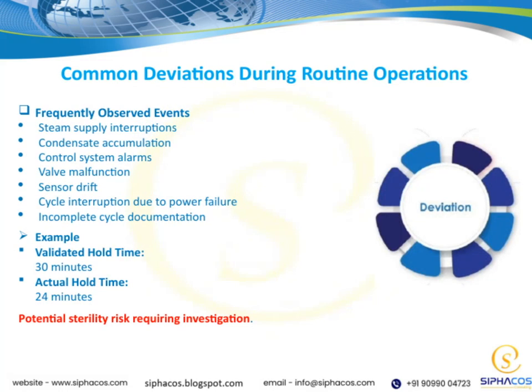When we talk about common deviations during routine operations, these are the events we see most often. Interruptions in steam supply, condensate buildup, alarms from control systems, valves not working right, sensors drifting out of calibration, cycles stopping because of power failures, and incomplete documentation of the process. For example, if the validated hold time is 30 minutes, but the actual hold time is only 24, that's a red flag. It could mean a potential sterility risk that needs immediate investigation.